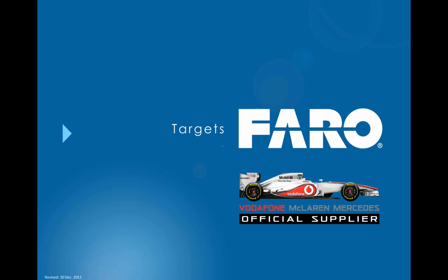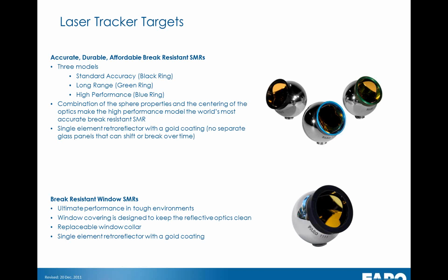So with any type of tracker, we have to have laser tracker targets as well. These are known as SMRs, or spherically mounted retroreflectors. And FARO provide these in 3 different sizes and in 3 different models as well as base models. So we have the standard accuracy reflectors, which we would call the black ring reflectors, our long-range ones, which have a green ring on them, and our high-performance reflectors, which have a blue ring on them. The difference being, the standard black ring reflectors have a centering accuracy of 7 microns.